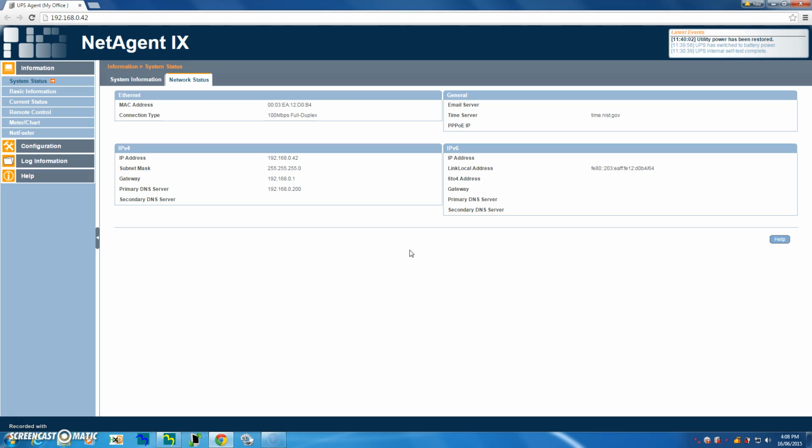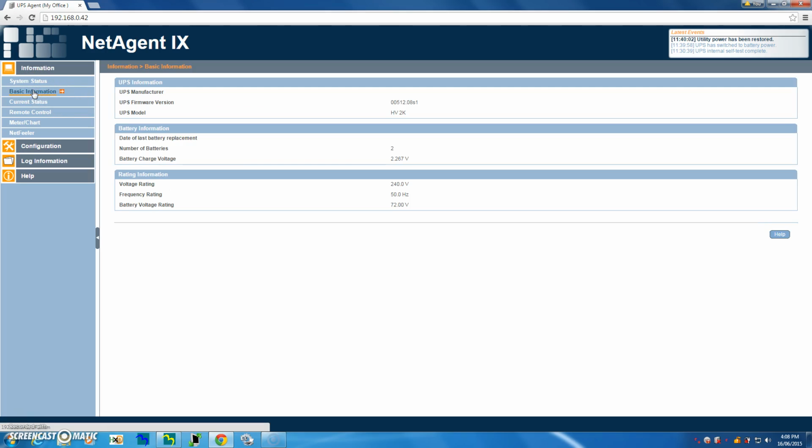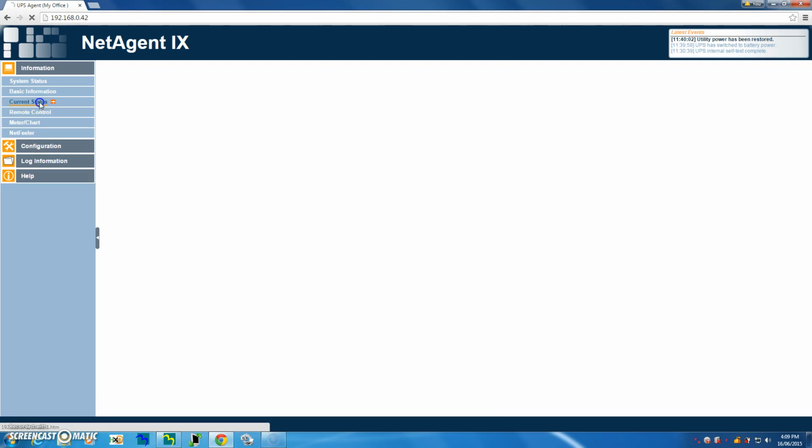What can you do in NetAgent 9 when you're on your internet browser? Well, you can look at your system status page and basic information, which will essentially tell you what firmware is installed in your UPS, what model UPS, in this case a 2KVA, and what ratings the UPS has. This UPS is rated at 240 volts, 50 hertz, and a 72 volt battery string, 12 times 6, so I've got 6 batteries in series in my battery string in the Centurion RT 2000VA UPS.